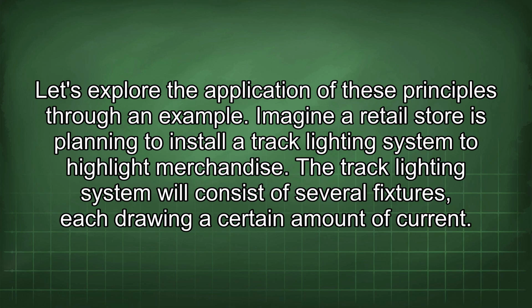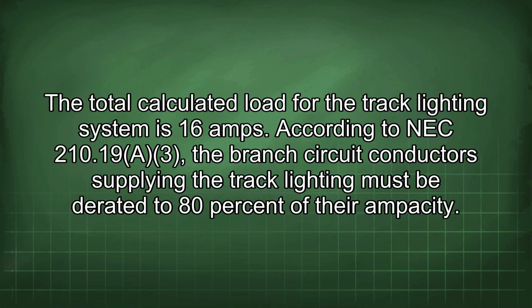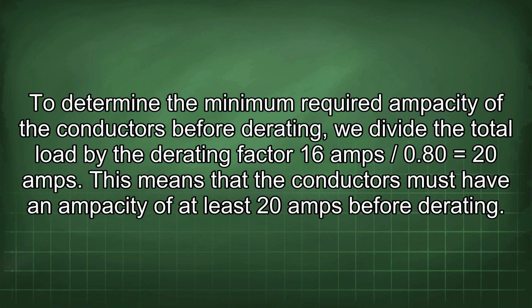Imagine a retail store is planning to install a track lighting system to highlight merchandise. The track lighting system will consist of several fixtures, each drawing a certain amount of current. The total calculated load for the track lighting system is 16 amps. According to NEC 210.19 A3, the branch circuit conductors supplying the track lighting must be derated to 80% of their ampacity. To determine the minimum required ampacity of the conductors before derating, we divide the total load by the derating factor: 16 amps / 0.80 equals 20 amps. This means that the conductors must have an ampacity of at least 20 amps before derating.